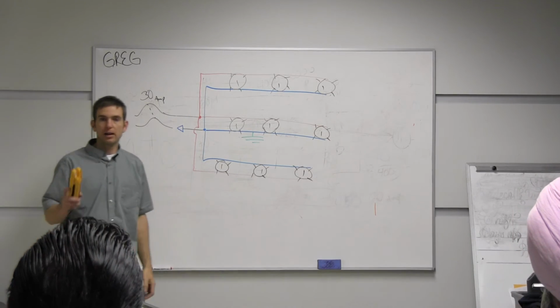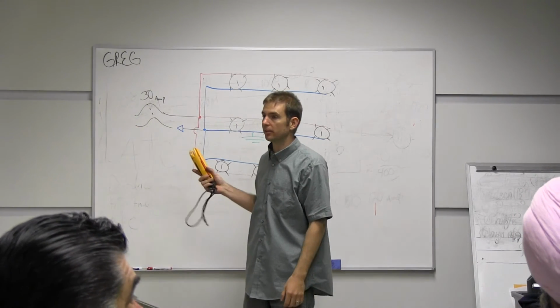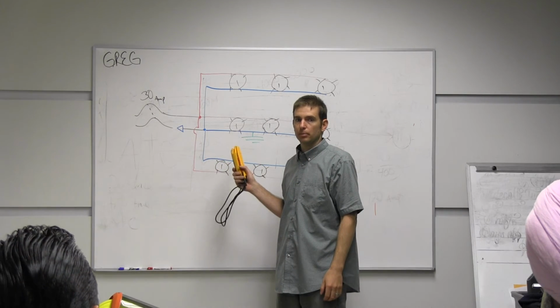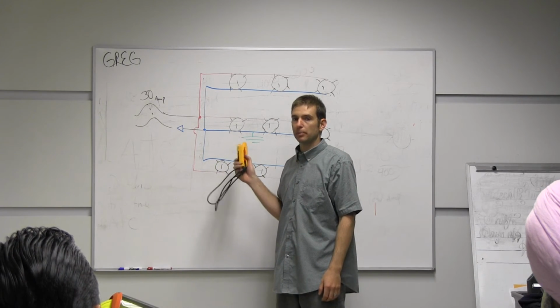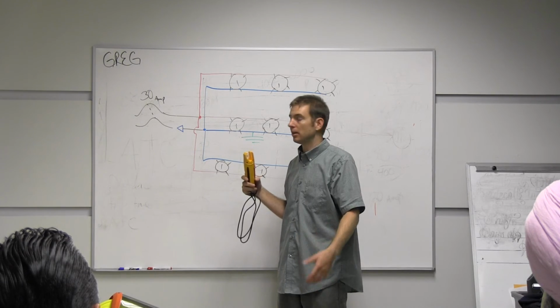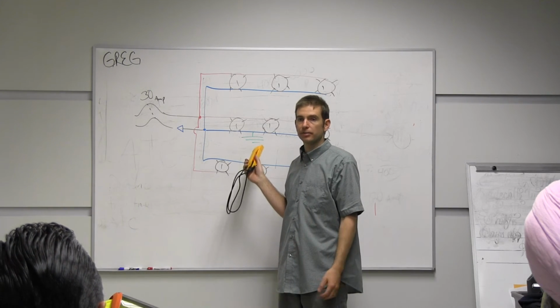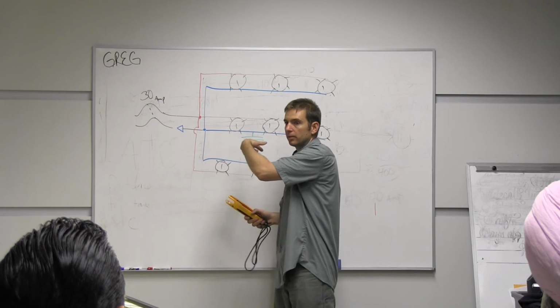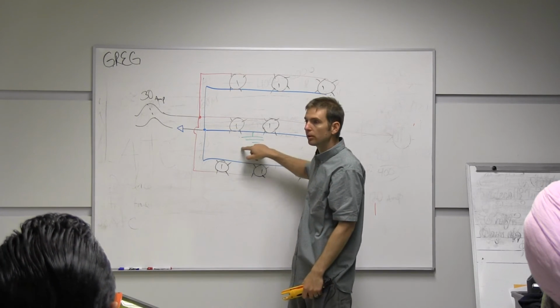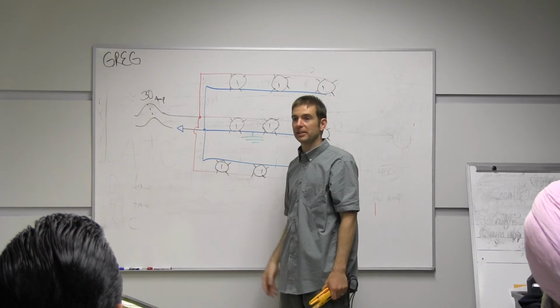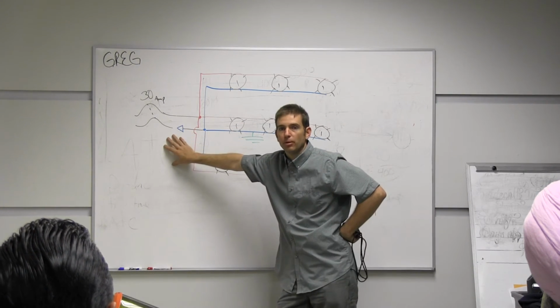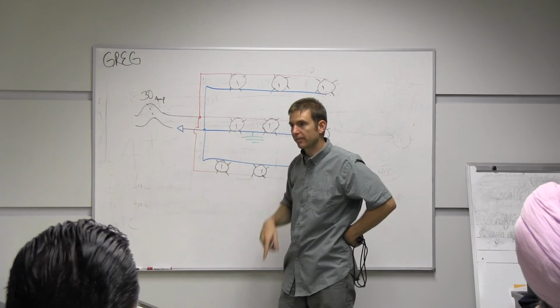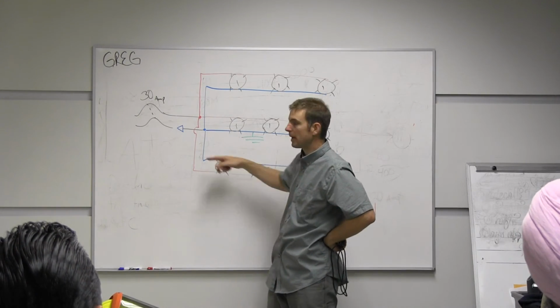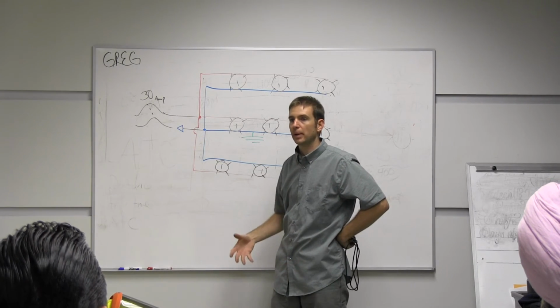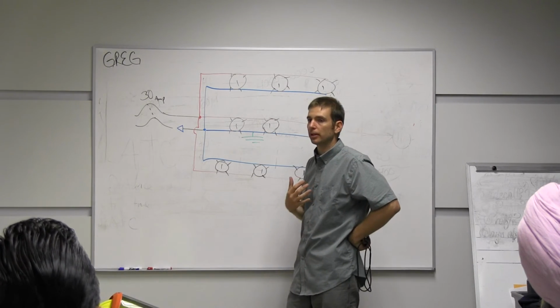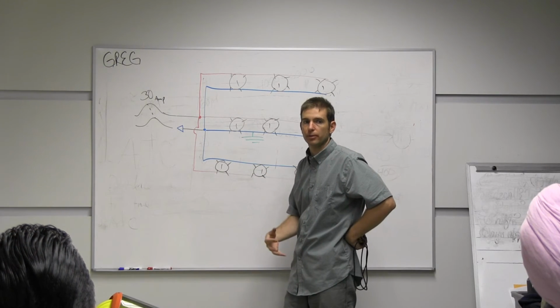This is grounded. Now I personally never do this and leave it overnight. But if I'm working on a circuit, I will do this. I'll let people know if there's people around. If I'm on the highway, I'll just do this during the day. At the end of my shift, I'll turn the circuit breaker off because I have voltage going through the ground, going through something. I don't want a pedestrian leaning up against a light pole or something that now they have current traveling through them because it's coming back to the source. It's going through the earth back to the transformer. I can't control it. I want to keep it on a wire. I don't want it to travel through the ground.